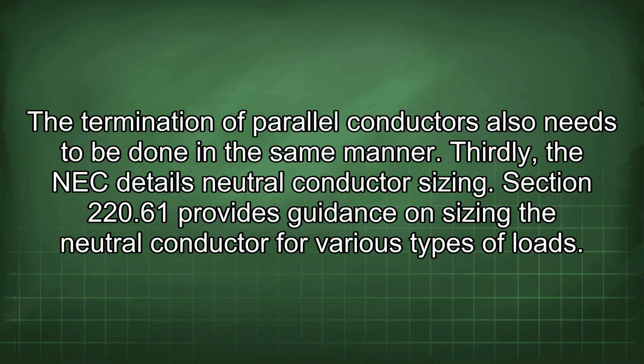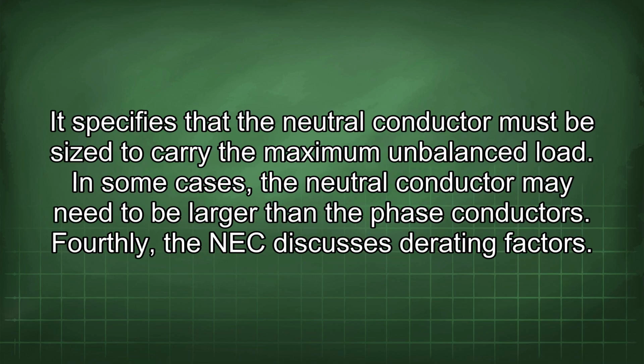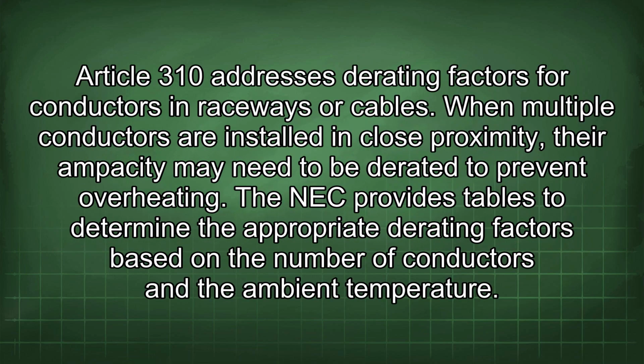Thirdly, the NEC details neutral conductor sizing. Section 220.61 provides guidance on sizing the neutral conductor for various types of loads. It specifies that the neutral conductor must be sized to carry the maximum unbalanced load. In some cases, the neutral conductor may need to be larger than the phase conductors. Fourthly, the NEC discusses derating factors. Article 310 addresses derating factors for conductors in raceways or cables. When multiple conductors are installed in close proximity, their ampacity may need to be derated to prevent overheating. NEC provides tables to determine the appropriate derating factors based on the number of conductors and the ambient temperature.